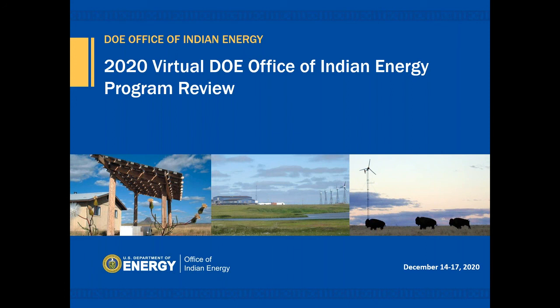Up until the last year that the tribe ran in parallel full-time with PG&E was 2004, and that year they had 52 power interruptions. What we qualify as a power interruption isn't necessarily what the utility counts. It was a power quality issue at the casino, basically almost one a week where they would have at least some type of brownout, if not a complete blackout. So we had to come up with some way to mitigate that.